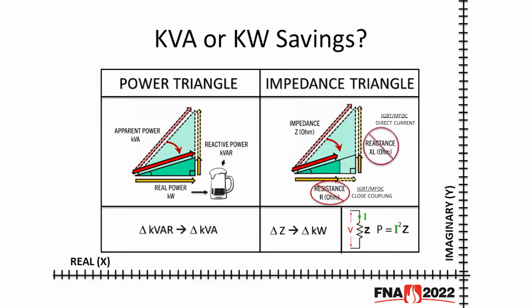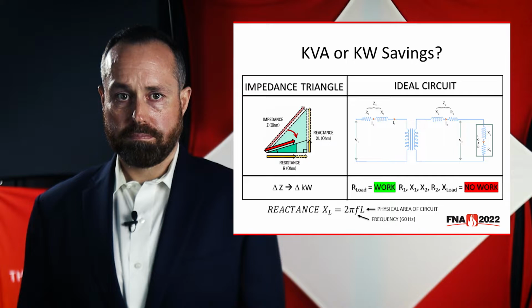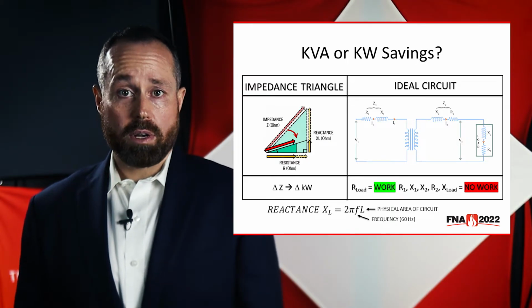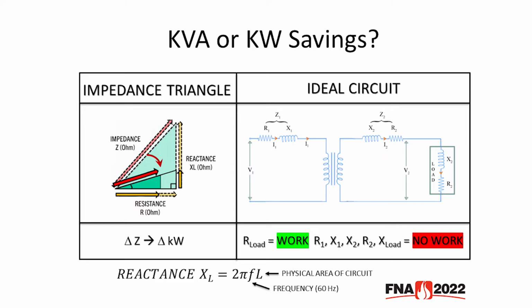And it lowers total resistance by shrinking the transformer and moving it closer to the heating elements with what we call close coupling. Here's another way to look at the impedance triangle and how it impacts power within a system. An ideal circuit is shown on the right. This circuit shows a standard impedance model of a transformer and load. This is essentially our standard model of a furnace heating circuit. The components of power include resistance and reactance in the primary circuit, resistance and reactance in the secondary circuit, and resistance and reactance in the load. The important note here is that the only component doing work is resistance in the load. The other components have no useful value, and every effort should be taken to reduce them.